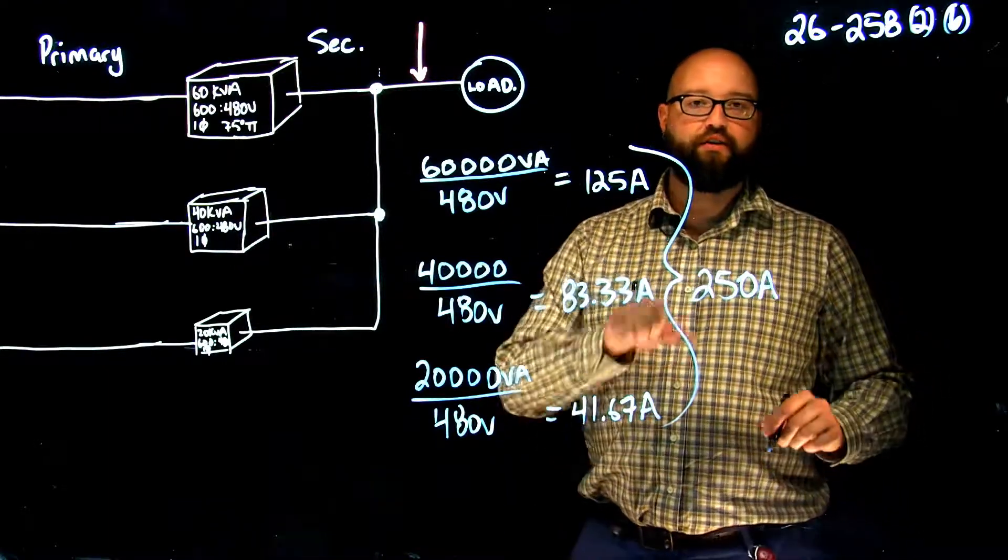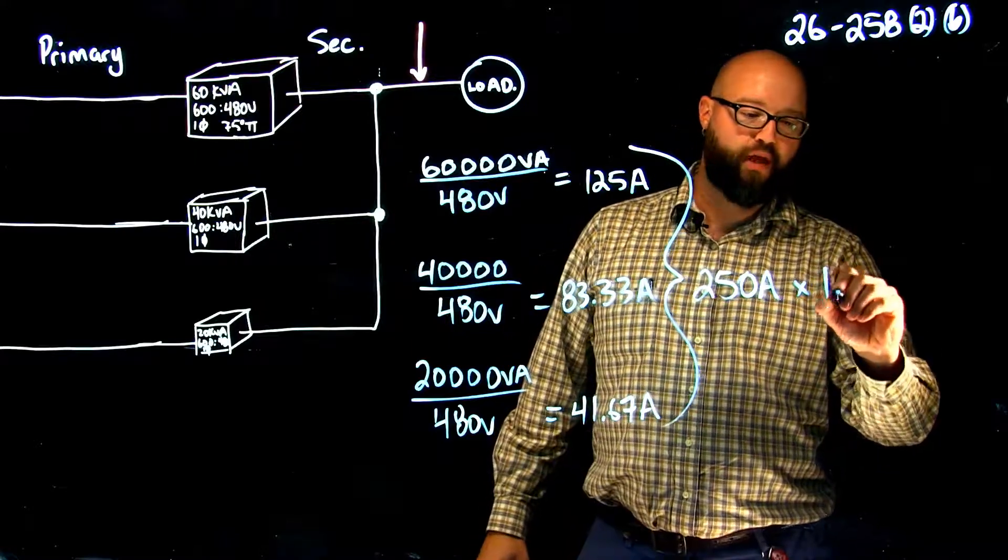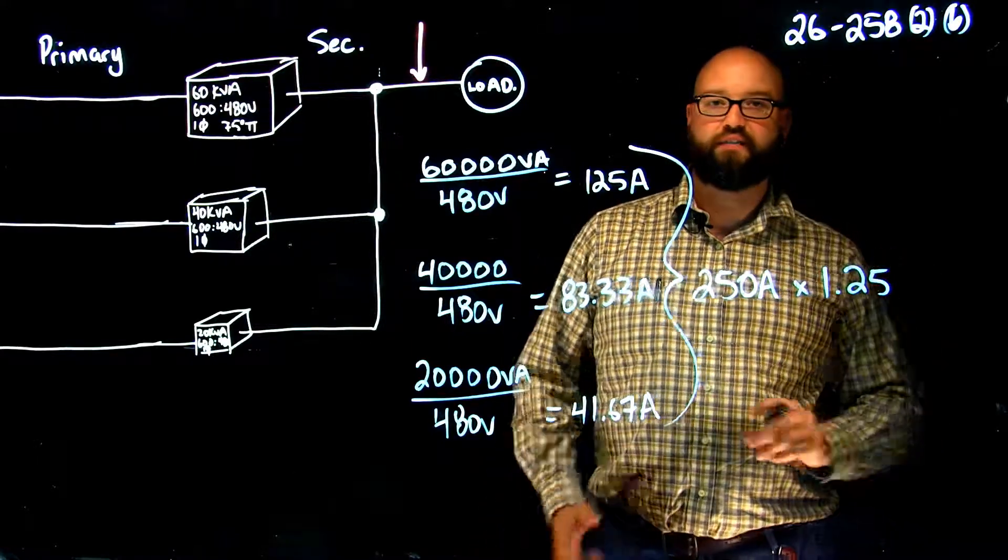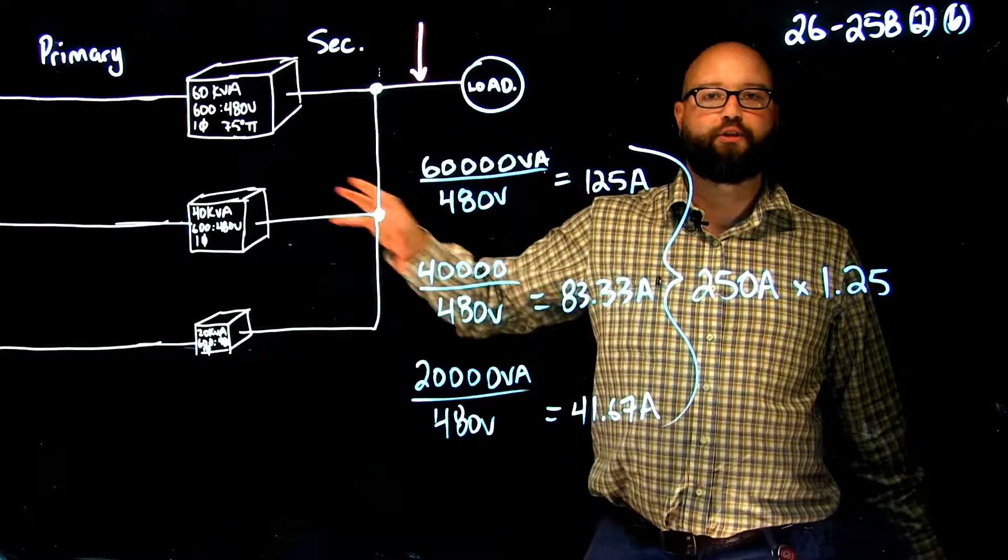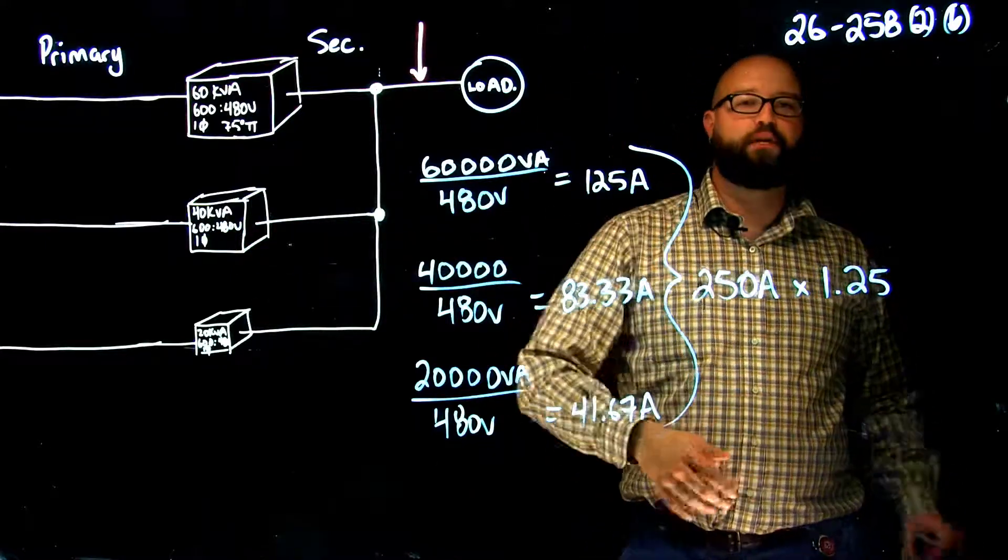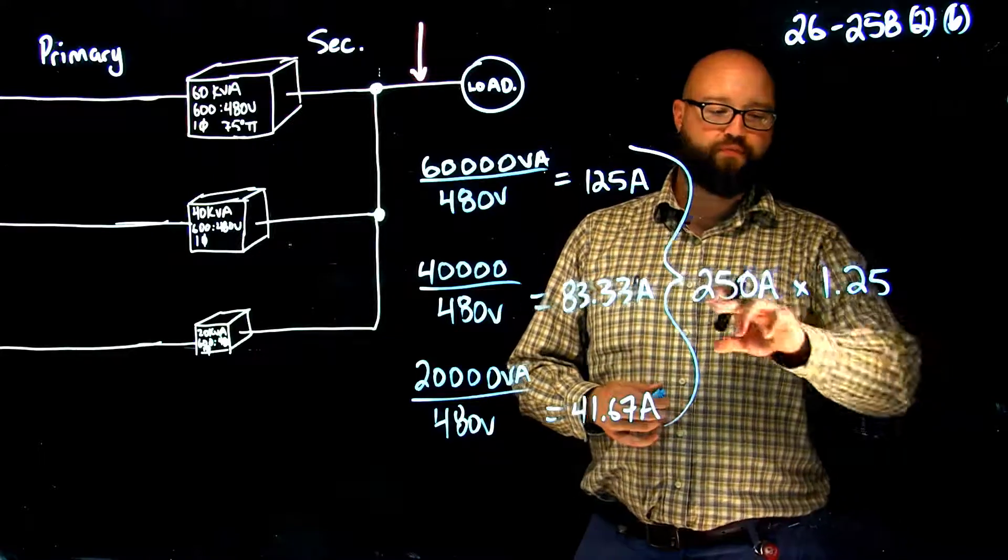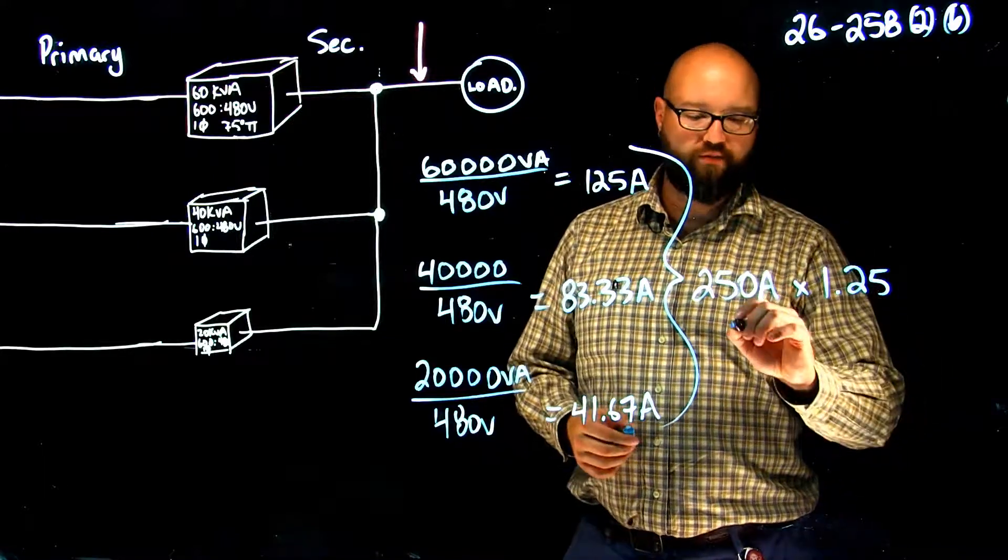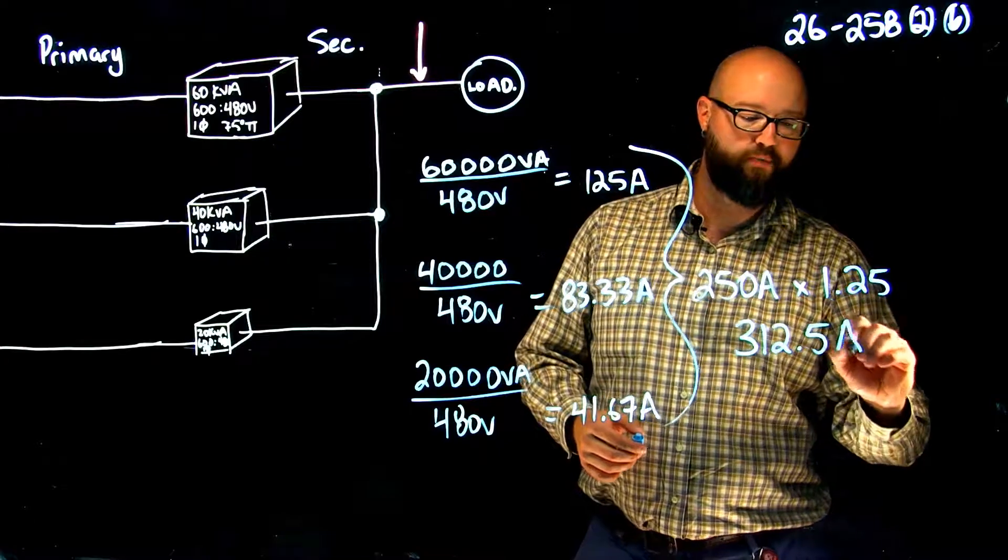Now we're going to take this entire number and multiply it by 1.25, that's the difference between the secondary parallel and the primary parallel. Now we're taking all of these values and putting them at 125%. 250 times 1.25 should give us a number somewhere around 312.5 amps.